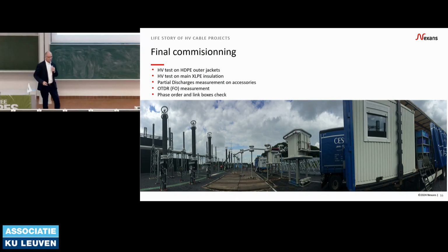Once your job is finished, you have to test it, because even though the cable was tested in the factory and the accessories were tested in the factory, you can't be sure the person who worked on the joint and termination did the job correctly. He might have made a mistake. So once again, we need to bring in electrical systems and electrical injection systems to make the final test, what we call the SAT, the site acceptance test, to cross-check all the electrical parameters of the cable, insulation, outer jacket, everything. And if we have optical fibers in the cable for data sensing or temperature monitoring, we have to check that the fibers are intact and in good condition.